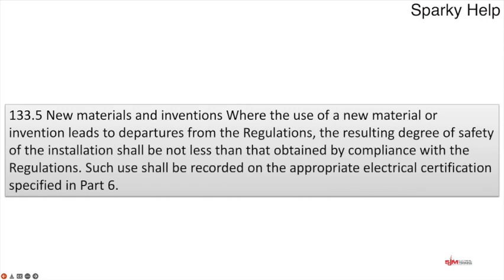The next one on there then, 133.5, it says new materials and inventions. Why you're making new materials and inventions, you might be, I don't know. There are lots of things that are constantly coming onto the market, but hopefully the manufacturer does actually test and check them for you, and therefore they do comply. But if you didn't, then it would be your responsibility to make sure that it does meet the requirements. And it says where the use of materials or invention leads to departure from regulations, the resulting degree of safety of the installation shall not be less than that obtained by compliance with the regulations, and it must be recorded on the test sheet. And that's the bit we were just looking at.